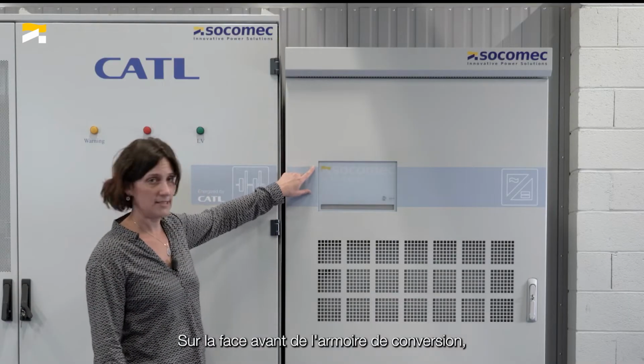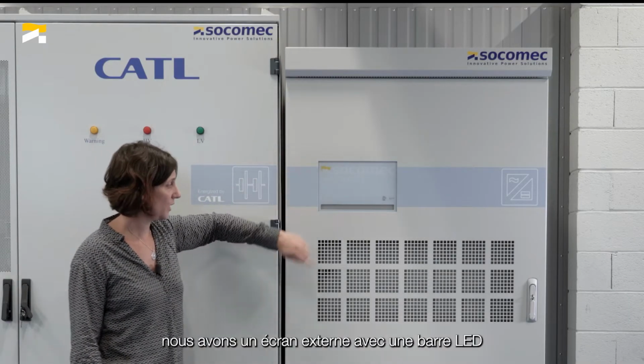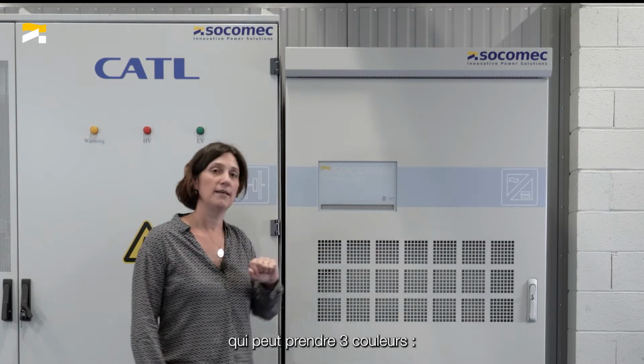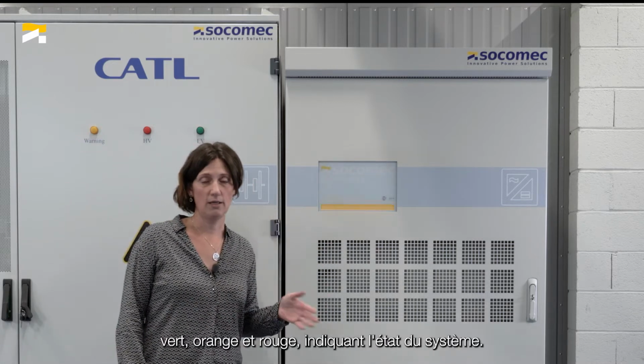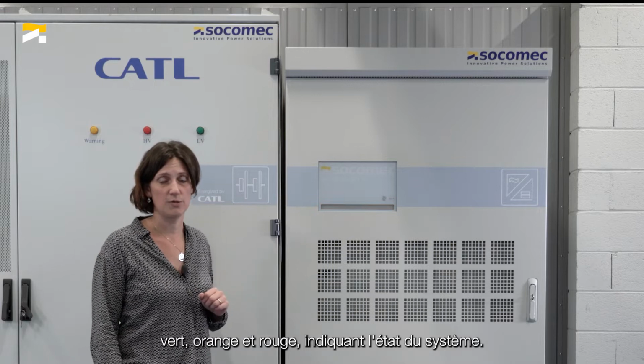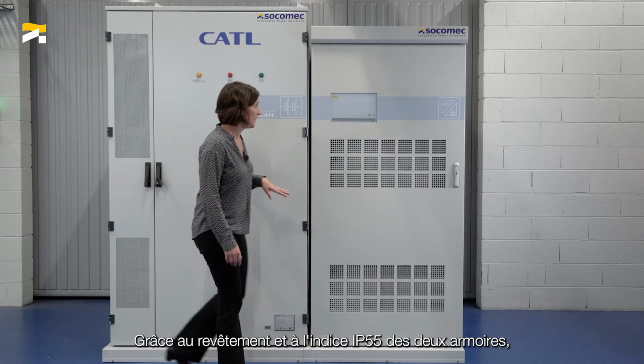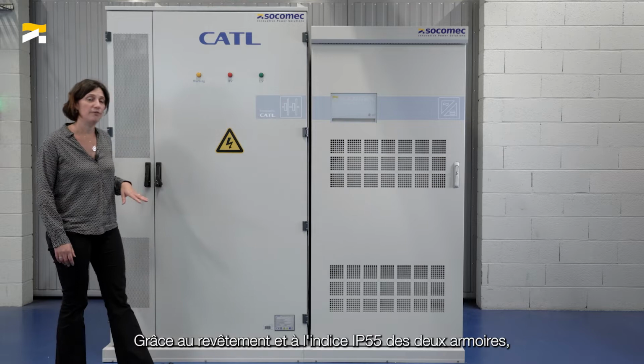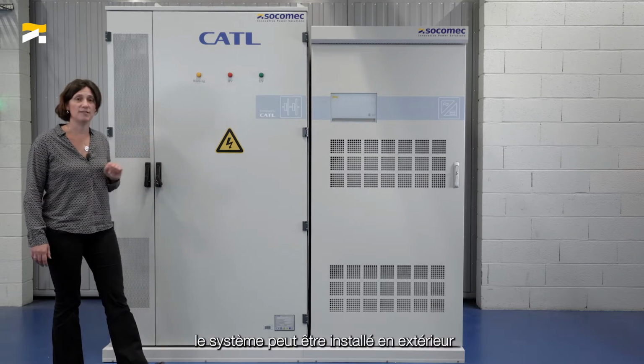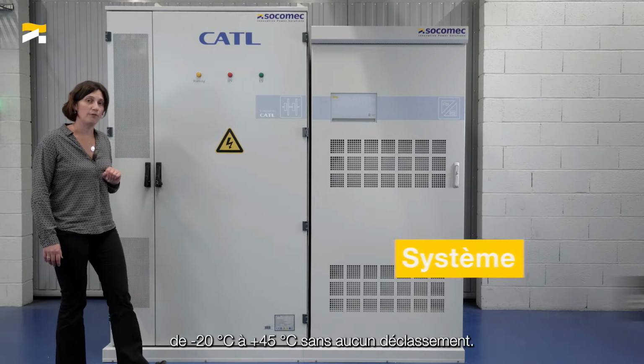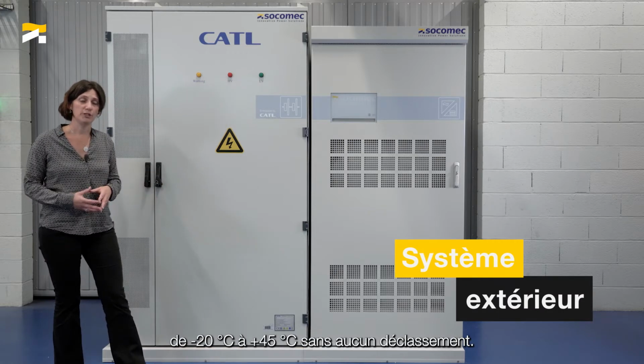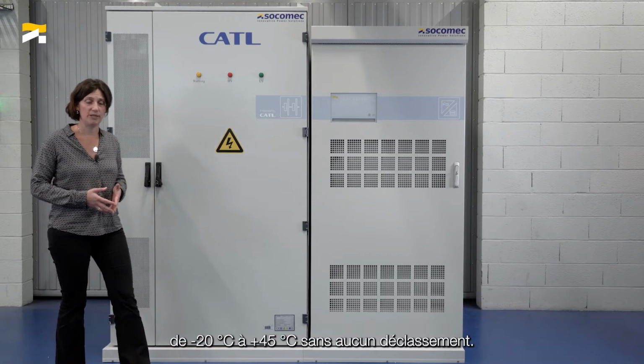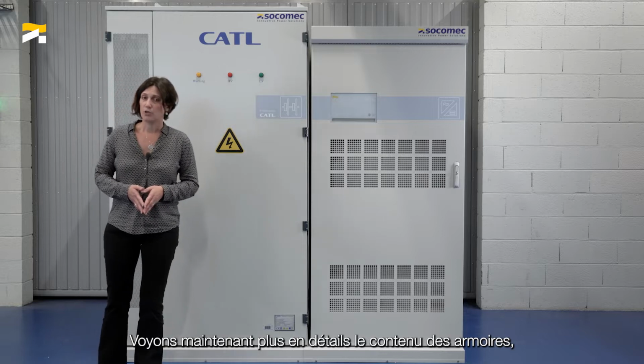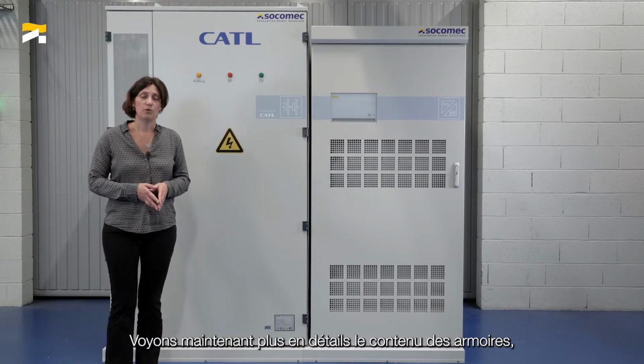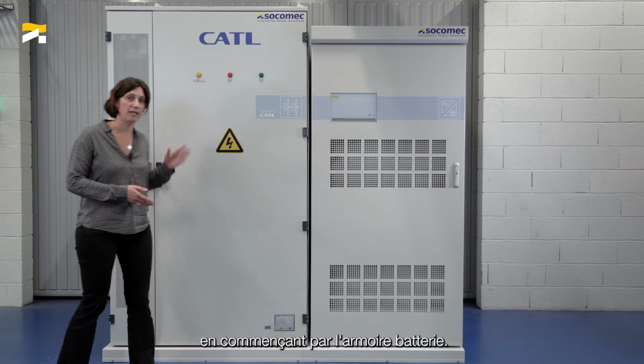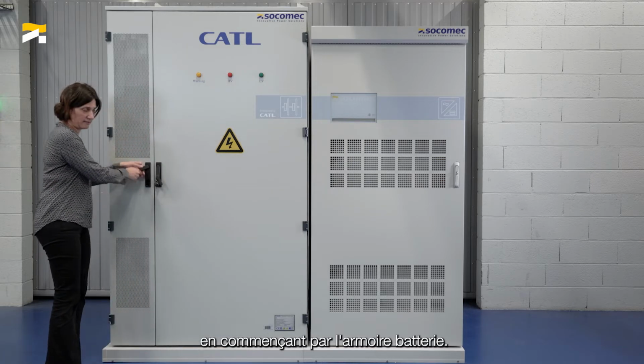On the front face of this latest cabinet, we can find a screen with a LED bar that can take three colors, green, orange and red, according to the system state. Thanks to the coating and the IP55 rating of both cabinets, the system can be installed outdoor from -20 up to +45 degrees C without any derating. I would now like to give you more details about the contents of the cabinets. So, let's begin with the battery cabinet.